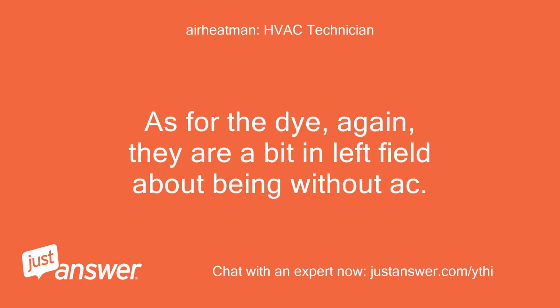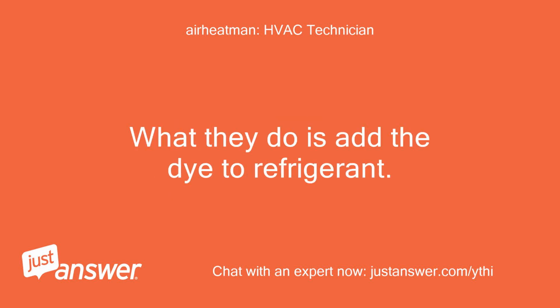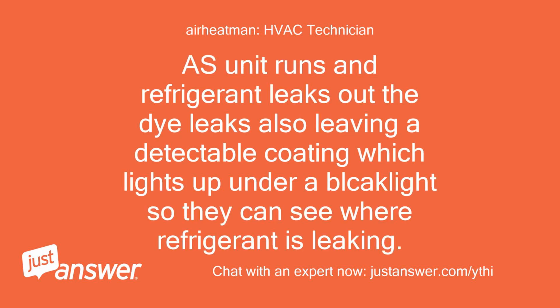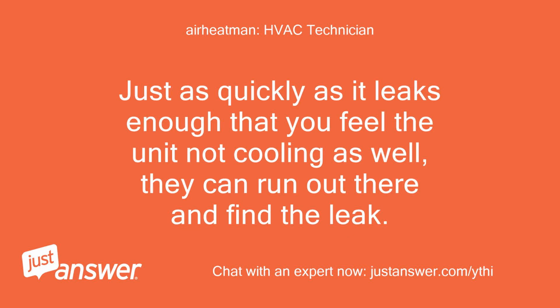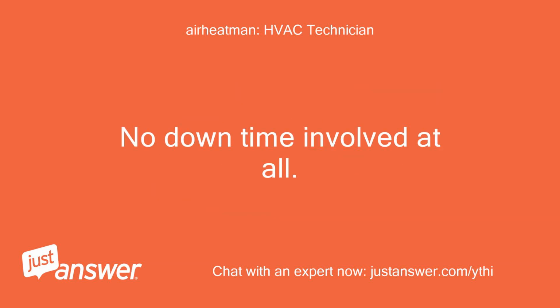As for the dye, again, they are a bit in left field about being without AC. What they do is add the dye to refrigerant. As unit runs and refrigerant leaks out, the dye leaks, also leaving a detectable coating which lights up under a black light so they can see where refrigerant is leaking. Just as quickly as it leaks enough that you feel the unit not cooling as well, they can run out there and find the leak. No downtime involved at all.